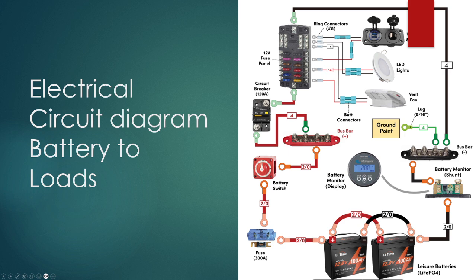In the fuse panel, normally on the upper side we have negative terminals, and we use ring connectors and butt connectors for our loads, which can be a socket, LED, or vent. Then one connection goes to the negative terminal, which is connected to the negative bus bar, also connected to ground point, and then to the battery monitoring system, and then it goes back to the battery.